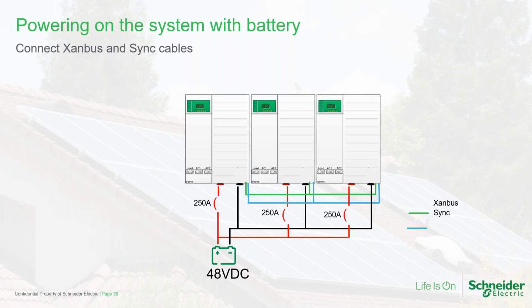The Xanbus network should be terminated, meaning no open Xanbus ports. Sync ports do not require termination. Each XW Pro has 2 Xanbus ports and 2 sync ports that allow daisy chaining of these devices together.